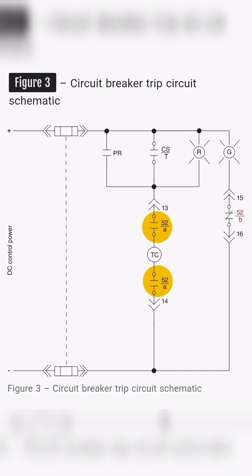Figure 3 shows the typical trip control circuit of a circuit breaker. The trip coil of the breaker is connected in series with auxiliary 52A breaker contact so that it only energizes when the breaker is closed and needs to be opened or tripped. This prevents damage to the trip coil should the trip signal remain on after the breaker opens and the control switch or protective relay contact is still closed. Either the control switch trip contact CS-T closing or any closing protection relay contacts PR will energize the trip control coil. The green light is powered by the normally closed auxiliary breaker contact 52B, so whenever the breaker is opened, the 52B contact closes and the green light becomes active, signaling that the breaker is open.